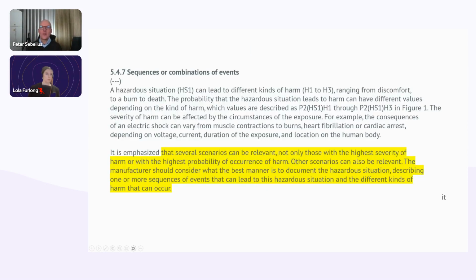This is the second half of 5.4.7, where it's stated that the hazardous situation can lead to different kinds of harm. The P2 can have different values. And at the end, it concludes that several scenarios can be relevant, not only those with the highest severity of harm or with the highest probability of occurrence of harm. Other scenarios can also be relevant. And the manufacturer should consider what the best manner is to document the hazardous situation, describing, look at that, 1 or more sequences of events that can lead to this hazardous situation and the different kinds of harm that can occur. So it's in there. It's in there for sure.